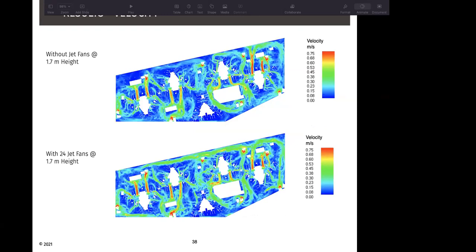Now, just to look at fan placements, what we have is the top image showing velocity around the car park without jet fans, and the bottom image showing velocity around the car park with 24 jet fans. Why we want to do that without the jet fans is because we want to understand what is the natural airflow path around the car park. So from the fresh air cutout, how is the air moving to the exhaust? Once we know that, we can optimize the number of fans that we require, because we can identify what are the stagnation zones or the underventilated zones around the car park. Also, we would want to maintain the natural airflow path and optimize that with the jet fans. So we do not want to move air against the natural airflow path, because that would be counterproductive. We want to maintain the natural airflow path and optimize the number of jet fans.